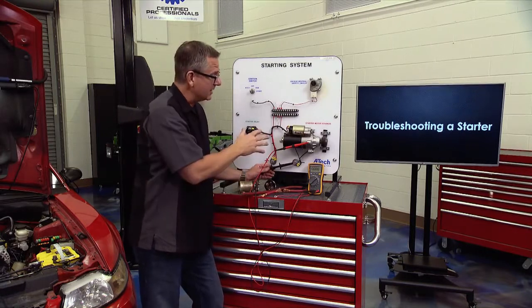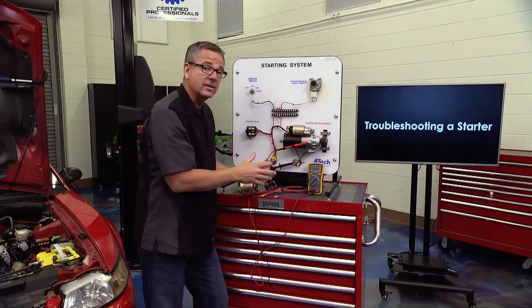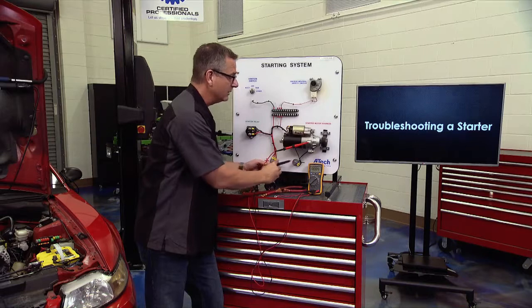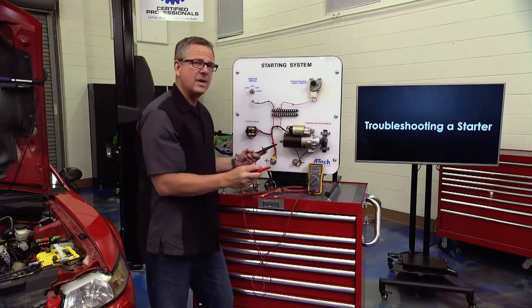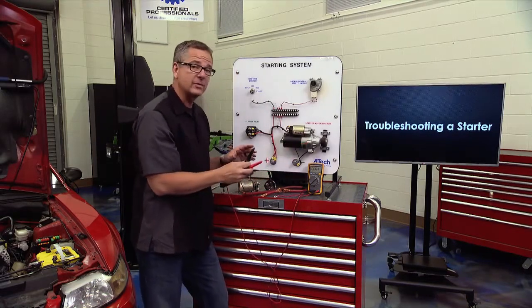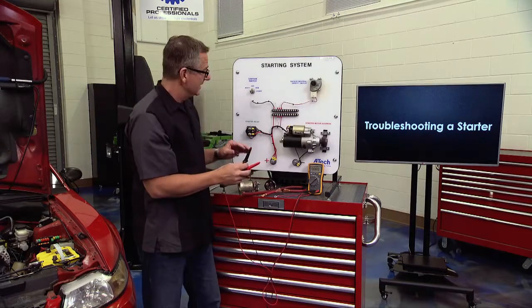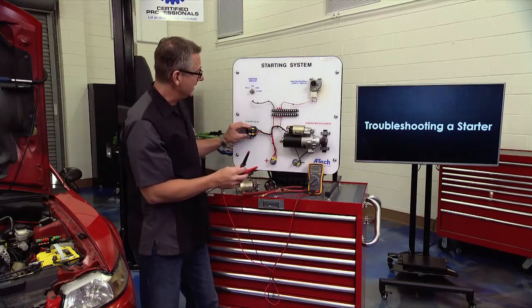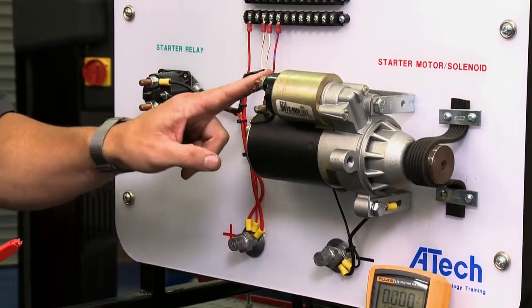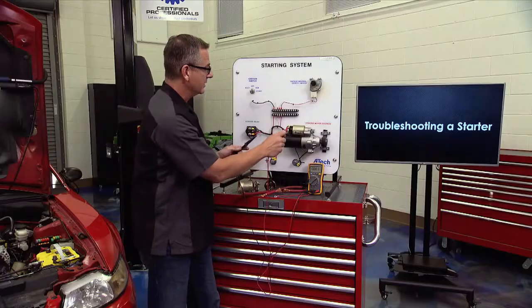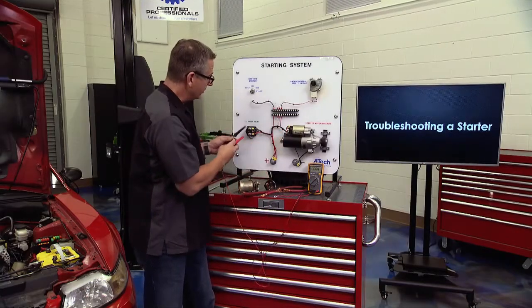Now, on our positive side we had a little bit, negative side we had a little bit, we were fine. But if we had a little bit more, let's say on the positive side, we can take it one step further and isolate it. Maybe it's just the contacts in a relay, or maybe it's this piece of wire from here to here. You can check all those. So I can go from here to here to check it, or I can go across the contacts.